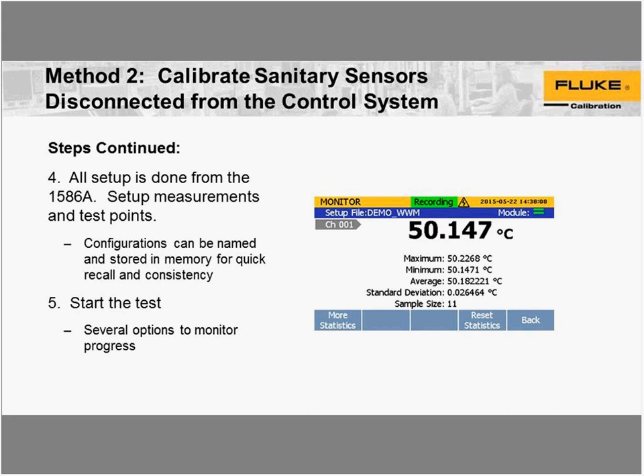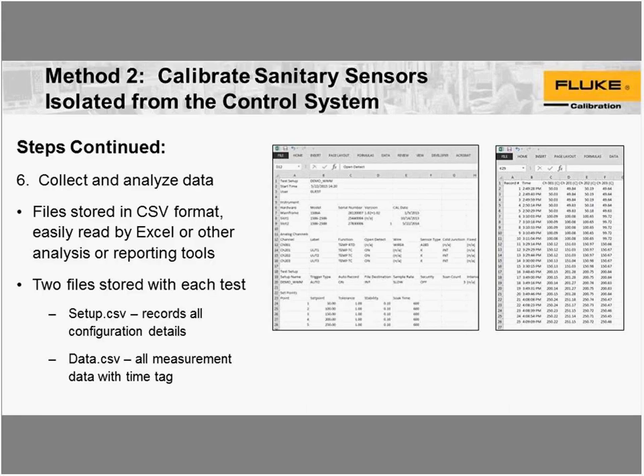You program in the points, then it can save the configuration in a file so that you can recall it if you need to use it over and over again. And then you start the test, and it will automatically run, soak, and take data. And when all data is collected, it will be put into a CSV file, and that can be opened in a spreadsheet. And from there, you fill out the calibration reports and then take a break.